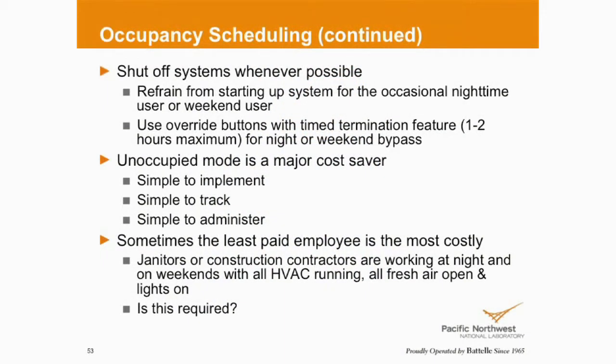Again, whenever possible, shut them down. If we keep starting up for the occasional nighttime user, weekend user, we're never going to win the battle. Do we have override buttons like we talked about earlier? In some buildings, we have provided that for people. We generally put them in the lobby or some place that is public. They know, hey, if I push it, I'm going to get 1 to 2 hours. It's real simple to program, real simple to add. It's what we would call low cost.